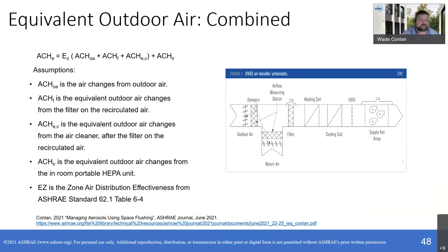One of the key things to focus on in that diagram is the order that it's in. It's a mixed air unit, filter, your coils, UV, and then your supply fans. And the order is important, right? So now we understand outdoor air, turn it into air changes, right? Lindsay showed us the calculations on how to get the air changes. So now let's take a look at the filter and what is its impact.